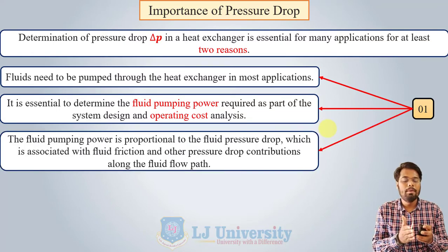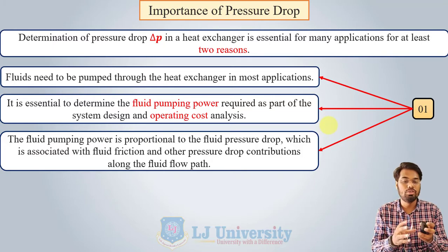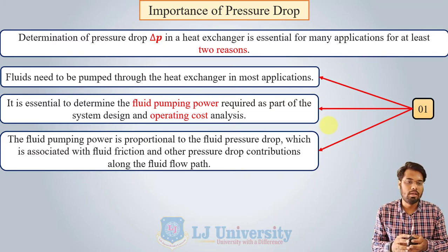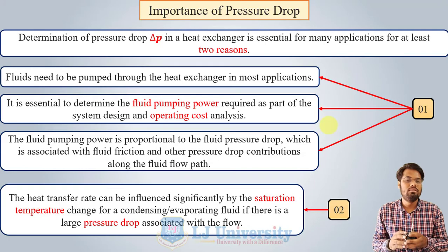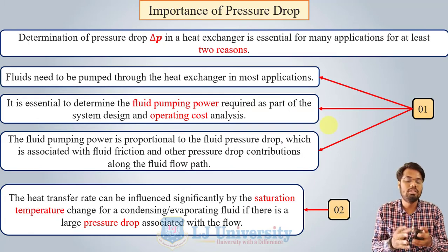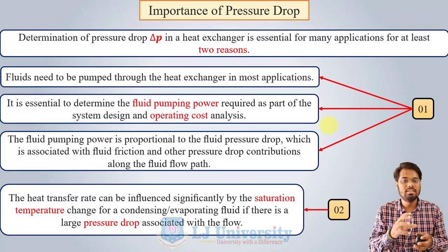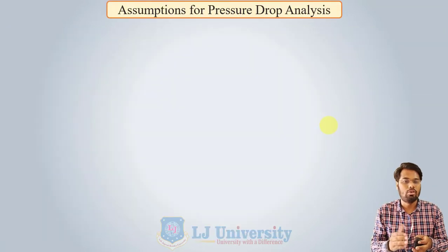The fluid pumping power, as we know, is directly proportional to the pressure drop, which is associated with the fluid friction and other pressure drop contributions along the fluid flow path. The second most important reason to determine the pressure drop is that the heat transfer rate can be significantly influenced by the saturation temperature, which is dependent on the pressure. So this is the second reason why we need to determine the pressure drop.